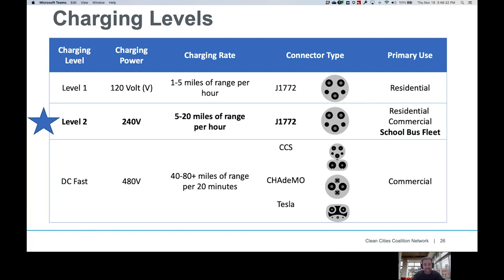Looking at both of those considerations, the sweet spot in terms of power delivery is really level 2 charging, which requires 240 volts of electricity and can give about 5 to 20 miles of range per hour of charge. It's a great sweet spot, typically able to refill a bus within a typical 8 to 10 hour dwell period, providing up to 19 kilowatts of power. It's a really great option for most applications, simpler to install than DC fast chargers, but much quicker to charge than a level 1 station.